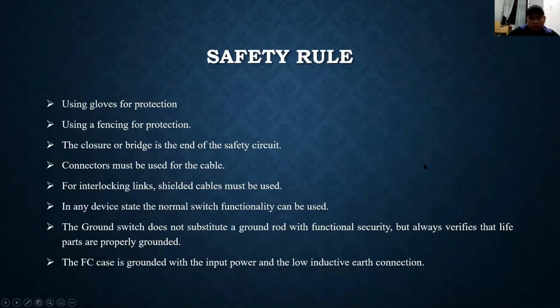So next, the safety rules. First, use gloves for protection. Second, use a fencing for protection. Third, the closure or bridge is the end of the safety circuit. Connector must be used for the cable. For the interlocking link, shield cable must be used. In any device state, the normal switch functionality can be used. The ground switch does not substitute a ground rod with functional security, but always verify that live parts are properly grounded. The FC case is grounded with the input power and the low inductive earth connection.